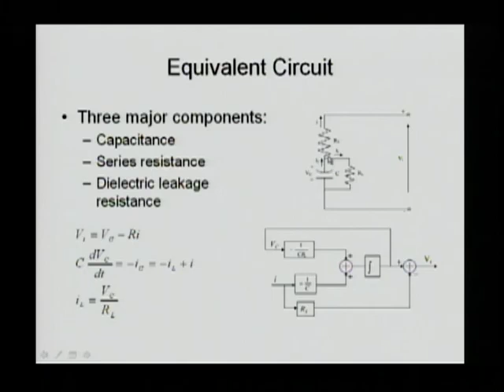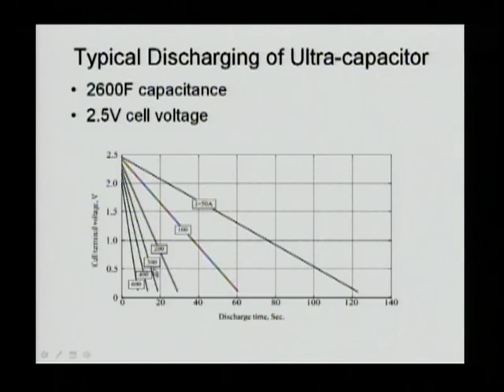For discharge of an Ultracap, as an example, a 2600 farad, 2.5 volt cell can be discharged at currents from 50, 100, 200, 300, 400 up to 600 amps. So it can be discharged at a very high rate, something a lithium-ion battery can never achieve.